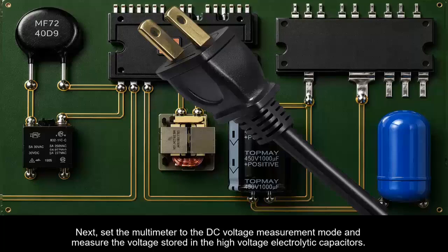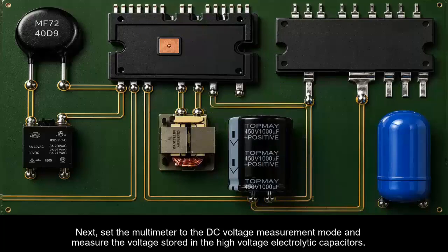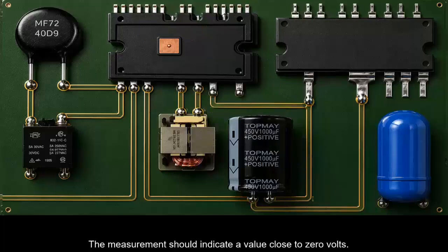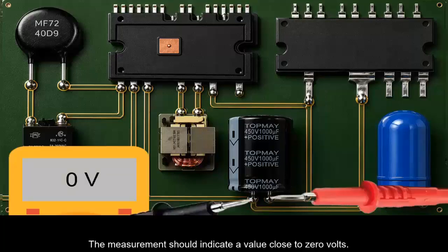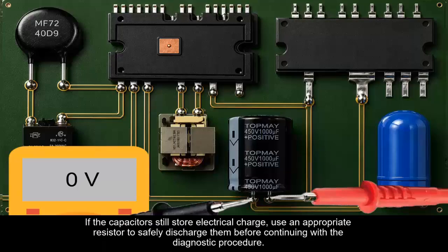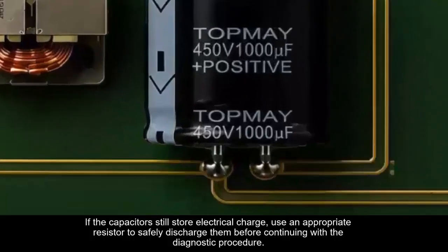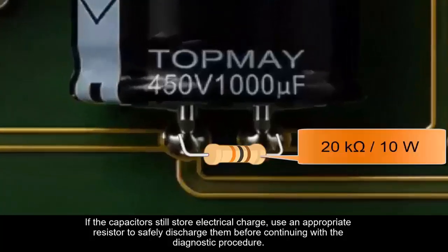Next, set the multimeter to the DC voltage measurement mode and measure the voltage stored in the high-voltage electrolytic capacitors. The measurement should indicate a value close to 0 volts.